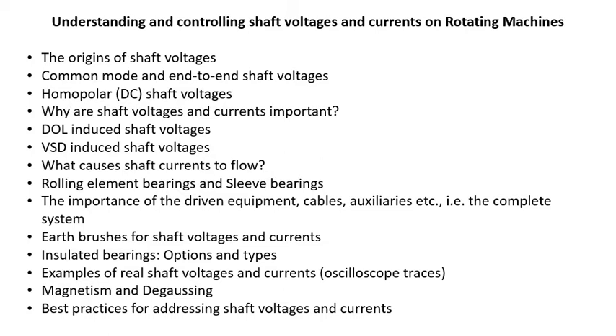It's those sad stories you hear when they did maintenance on a powertrain and afterwards the gears were melted and whatever. Why are shaft voltages and currents important? Well, obviously because they damage machines. Well, the voltages don't, but the currents that flow do. DOL induced, so sinusoidal. VSD, I can brush through that fairly quickly because Stian's done most of it.